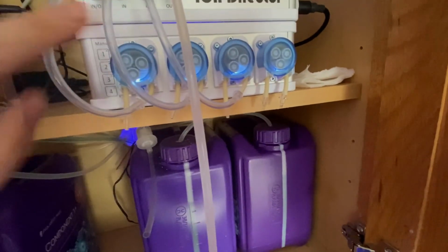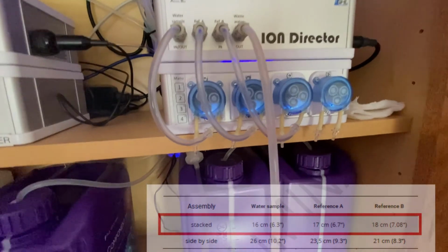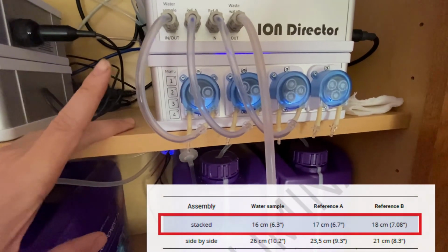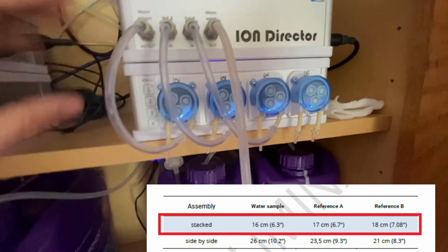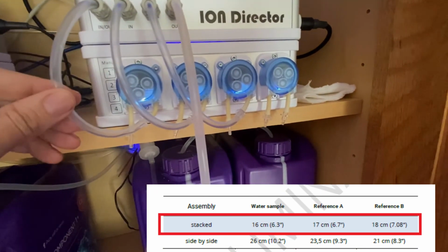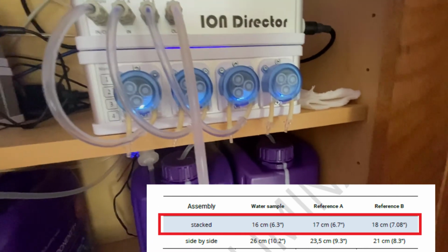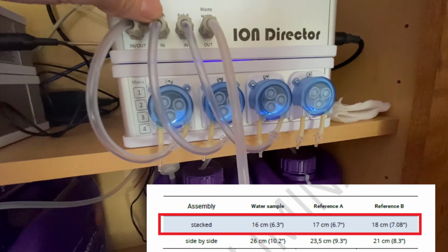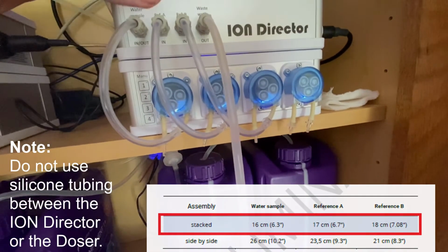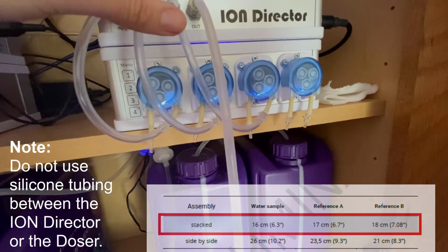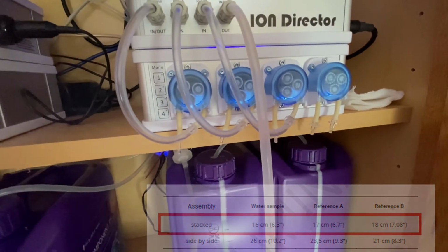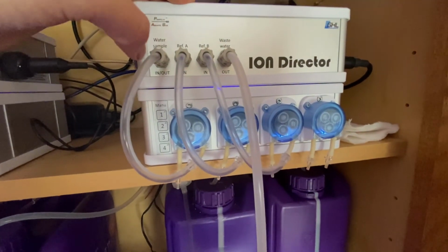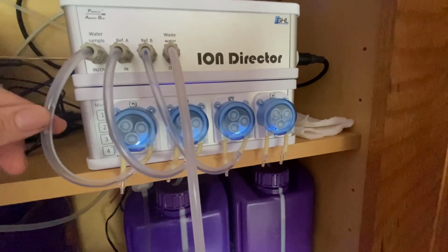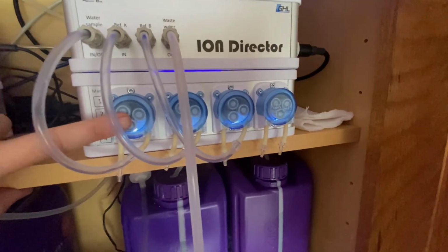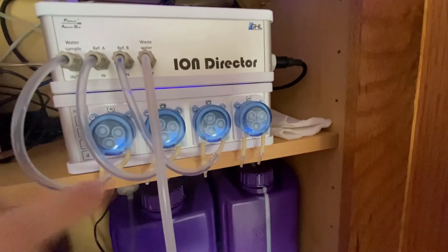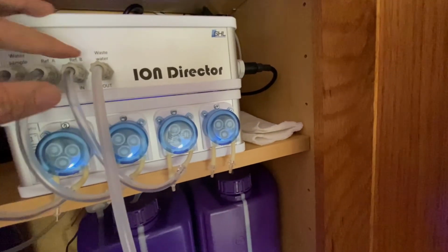The understanding is that the lengths of each one of these tubes is determined by the chart that I'm showing now, which is used in a stacked configuration. If it was side by side, these tubes would be cut differently. It's very important that you follow those tube lengths, measure a couple times. The other thing is, do not use silicone tubing on any one of these tubes. You should use the tubing that came with the ion director or PVC tubing. And again, I did it from the first tube, going from the first doser to the water sample, second one going to the reference A, and the third one going to reference B.